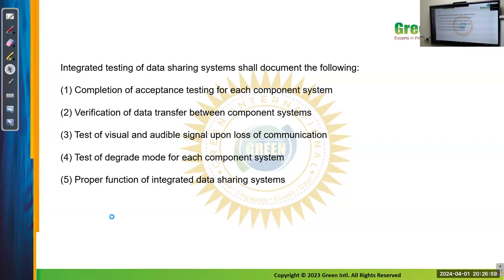Integrated testing of data sharing systems shall document the following. Once the testing is done, we have to document all these things. Completion of acceptance testing for each component system. Verification of data transfers between the component systems. That is in the panel, if all the systems are interrelated and working. It means if there is any incident of fire, the AC has to shut down, and the ventilation has to be working properly, and the sprinkler has to start automatically in the event of, let's say, one command or two commands based on the sprinkler system.